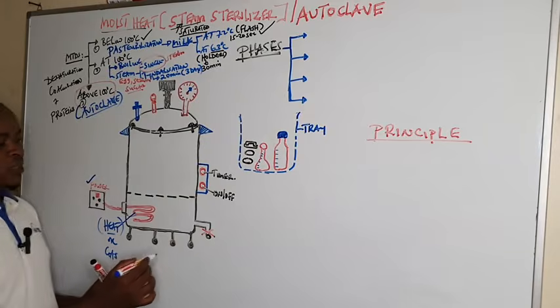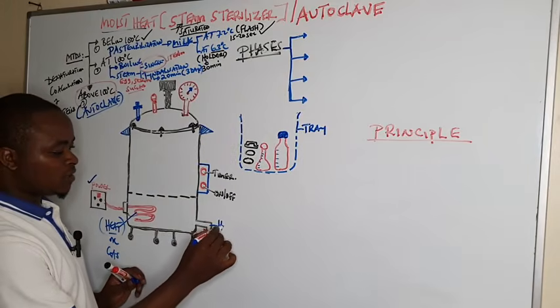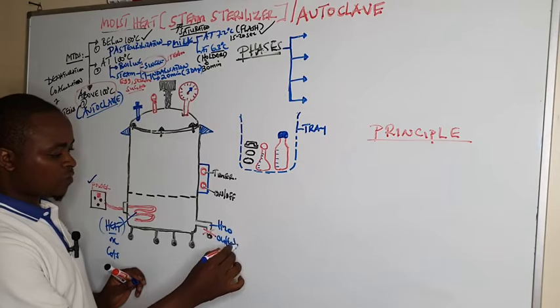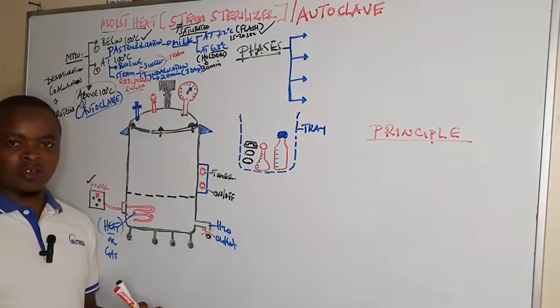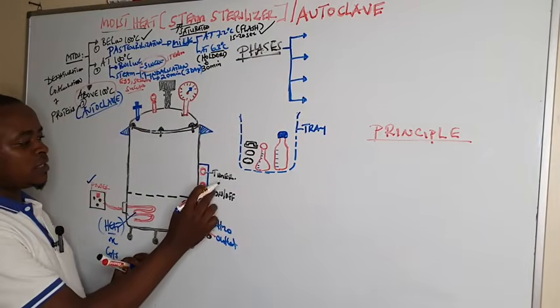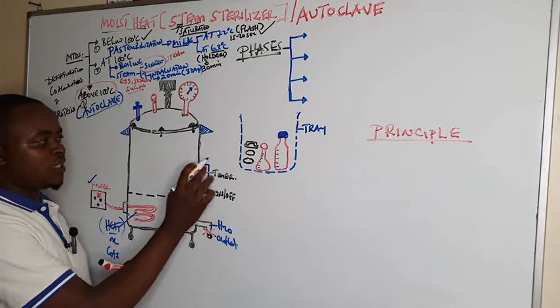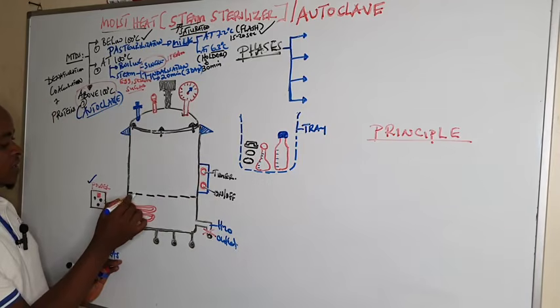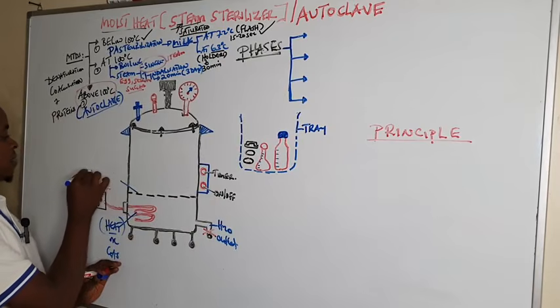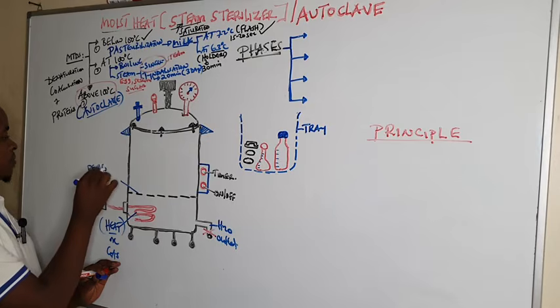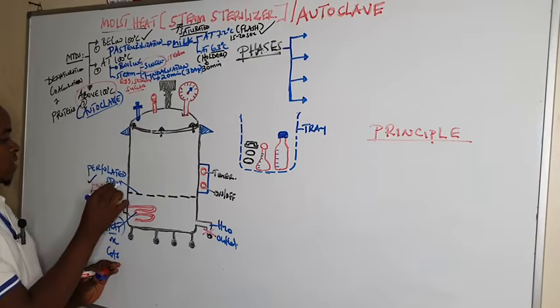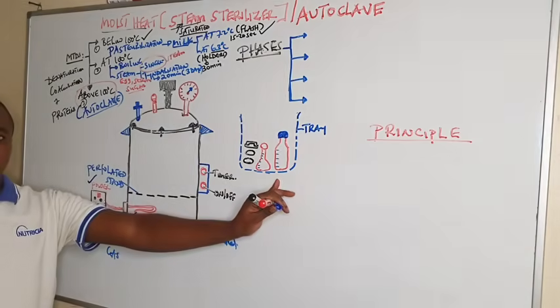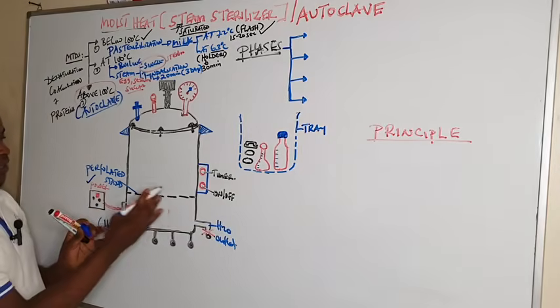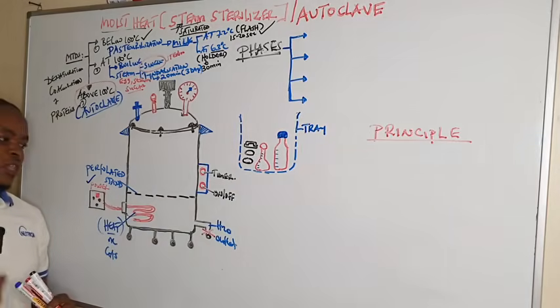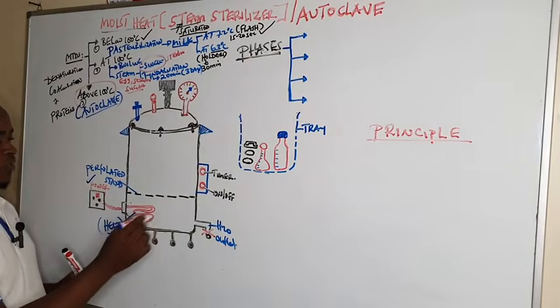And this autoclave has the water outlet. After sterilization, you can open it to drain the water when it is dirty. Then this is the switch where we can switch on and off, then the timer, and then we have the perforated stand. This is the perforated stand where we place our loaded tray. Our loaded tray is placed on this perforated stand within the autoclave after filling with water.